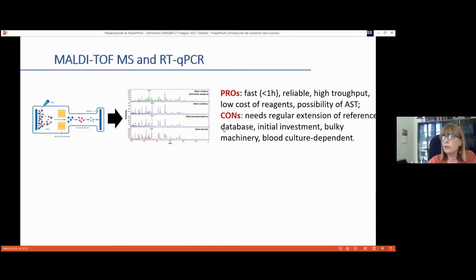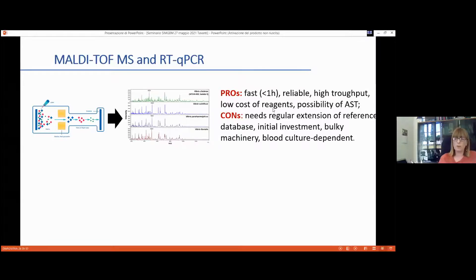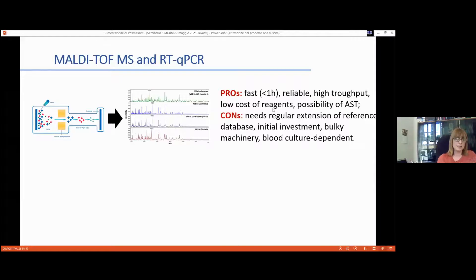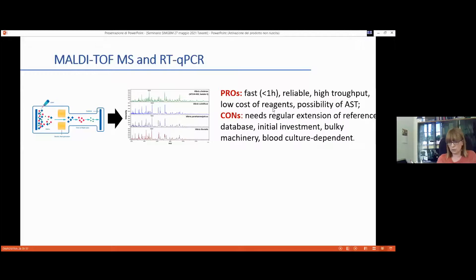MALDI-TOF mass spectrometry in larger laboratories offers fast, reliable, high-throughput identification within minutes of culture positivity. Reagents are not particularly expensive and antimicrobial susceptibility testing is possible. However, limitations include the requirement for continual database updates — a crucial point for robust diagnosis — a high initial instrument investment, and the instrument being bulky and difficult to make portable.